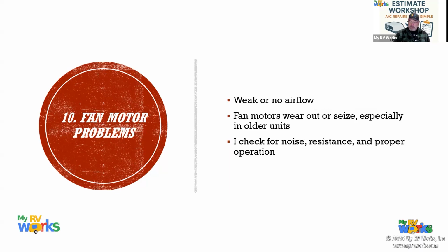The fan motor might have a problem. We just replaced one not too long ago. The thing was squealing, and the bearings seize up on these things, get dry. I know on the Colemans, the little low end Brisk ones, they have the air being blown outside through the condenser fin right at the motor, and the bearings dry out because you've got all this hot air blowing on them. They didn't check with me. I would have blown it the opposite direction, but they're blowing it onto the motor, so it's kind of backwards.